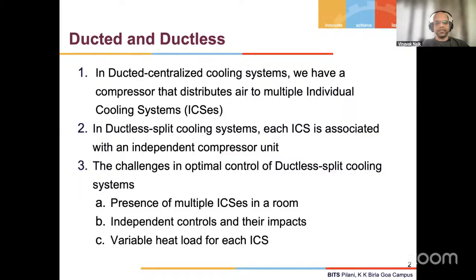We have multiple ACs, split units, in a room. Every AC has independent control and a different impact on cooling inside the room. Also, because of its proximity or location, every AC faces a different heat load. Some need more cooling just for warm air, for example one next to a glass window with direct sunlight, or more people sitting in one corner, or machines like servers running on one side creating more heat. We have to consider all these challenges to come up with optimal control.